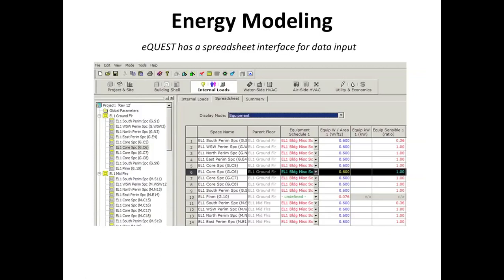To give you an idea of the level of detail that this software has, we can go in and pick specific zones. We can assign equipment load for that zone. We can adjust the equipment sensible heat output. If we're talking about maybe a commercial building that has a lot of process equipment, has a server room, we can go in and plug in specifics about what equipment's in there and how much heat is given off to the space.